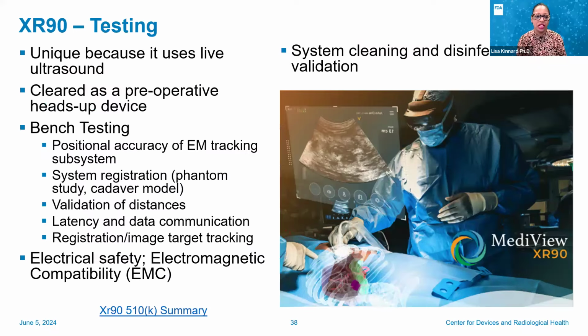This device is unique because it uses live ultrasound imaging. It has been cleared as a preoperative heads-up device, but not yet in the intraoperative space. They had to do quite a bit of testing, including a lot of bench testing for latency, accuracy, and similar factors. They also had electrical safety testing because some devices were their own in-house development. There was also system cleaning and disinfection testing, because while this is not an intraoperative device, it is used in the intraoperative space, requiring that type of testing.